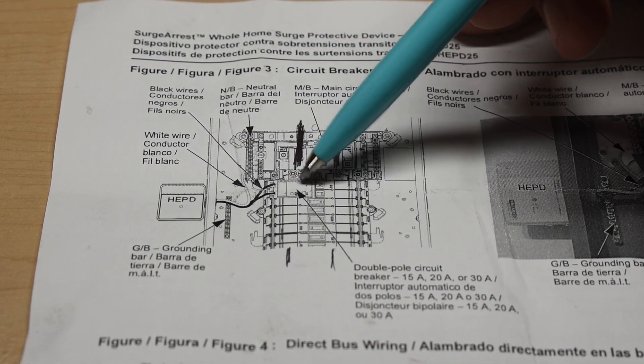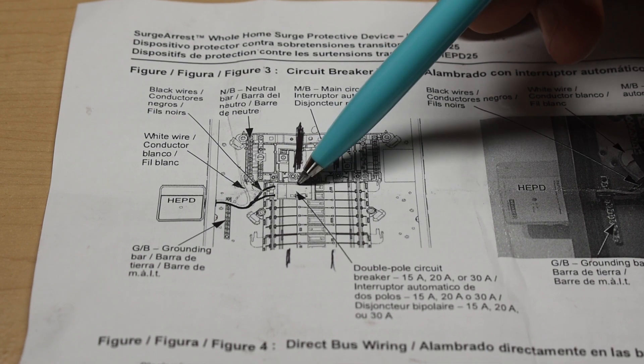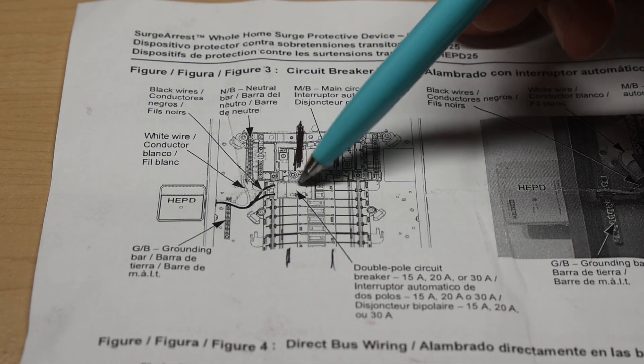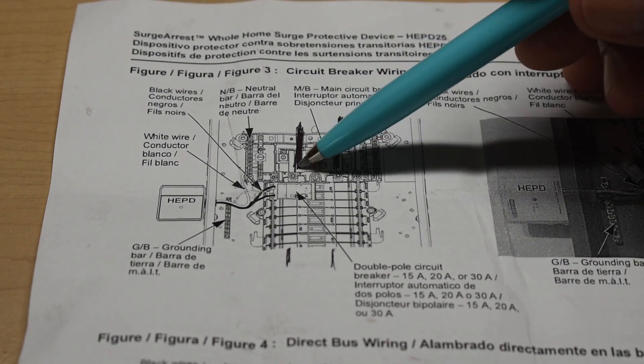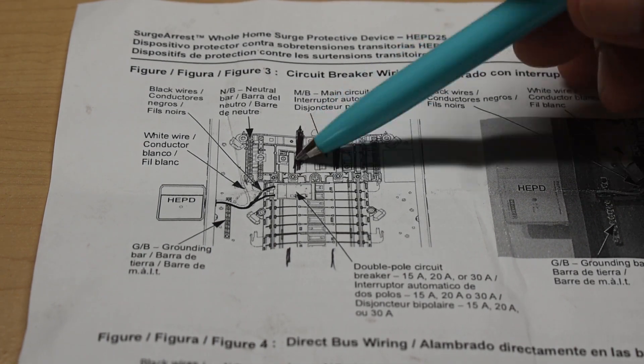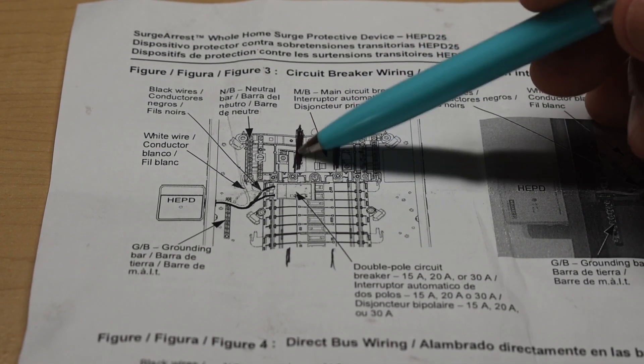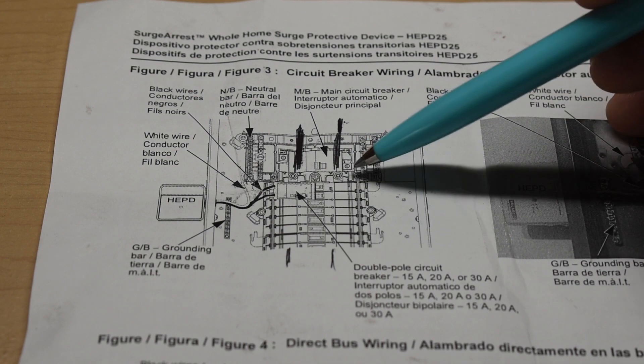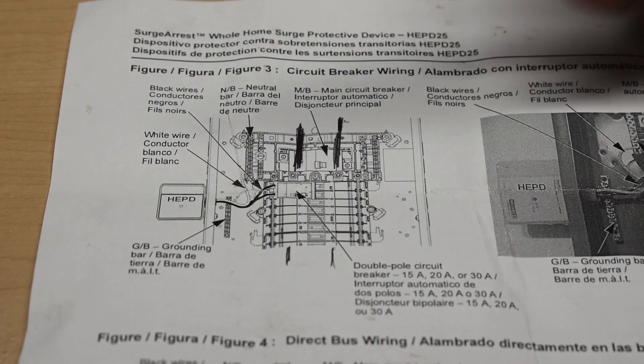Now, if you don't have a double pole breaker, you can also use two single pole breakers. But it's extremely important that both single pole breakers are not on the same bus bar. So make sure that one is clipping in to this bar and the other one is clipping into the opposite bar. Then you can do exactly as shown.